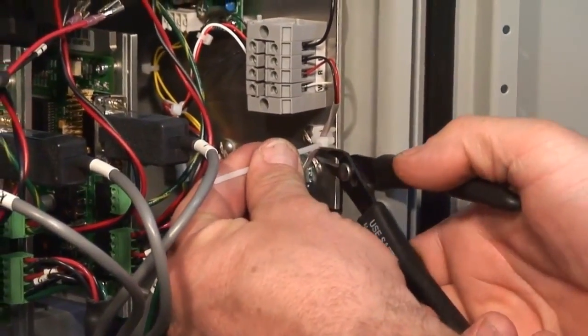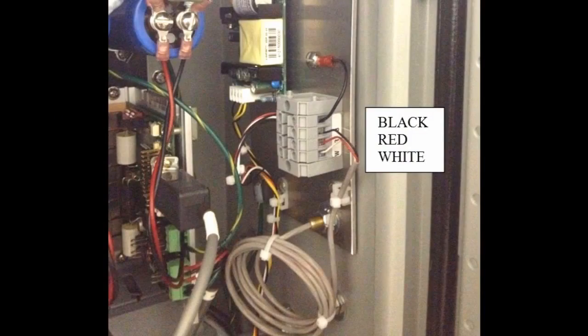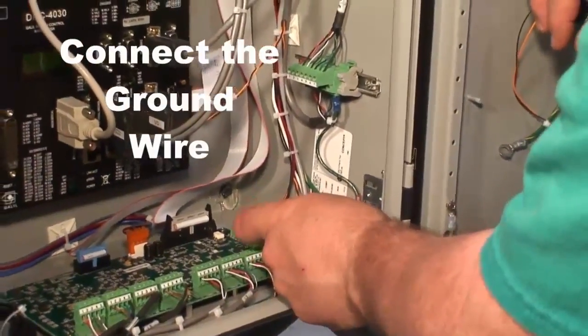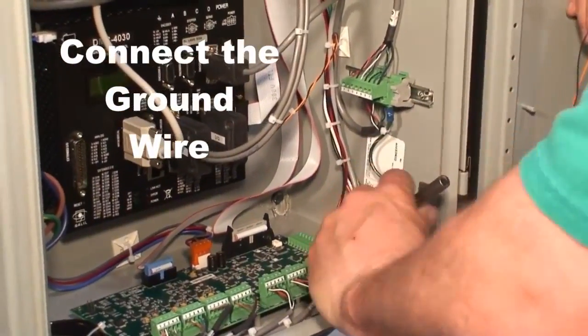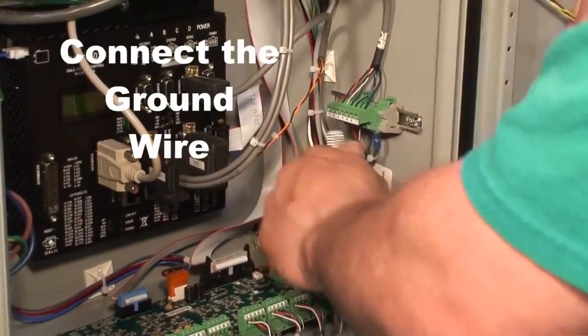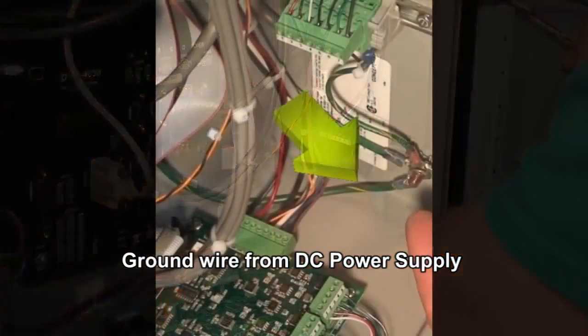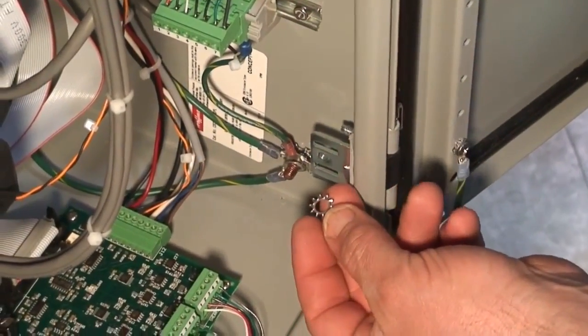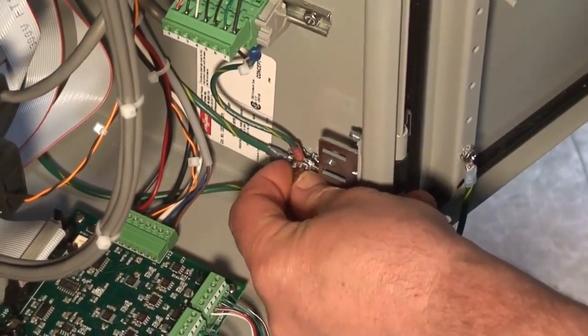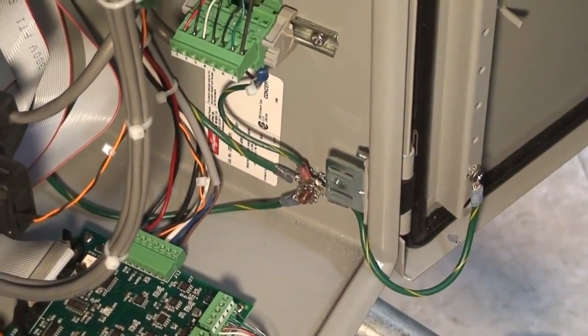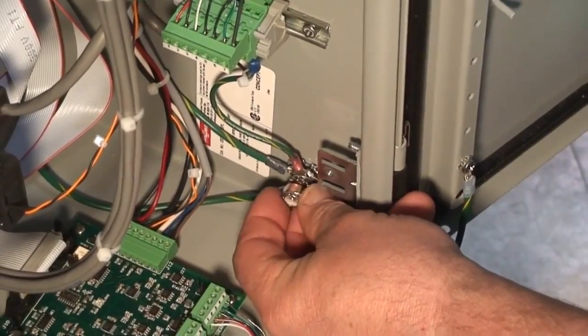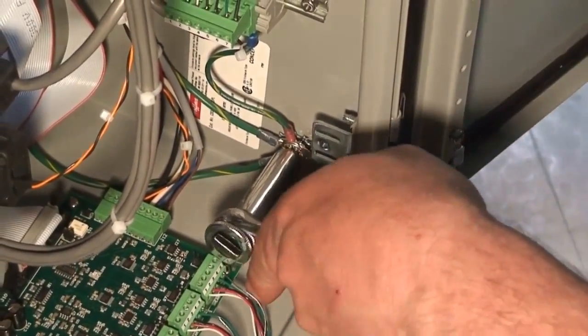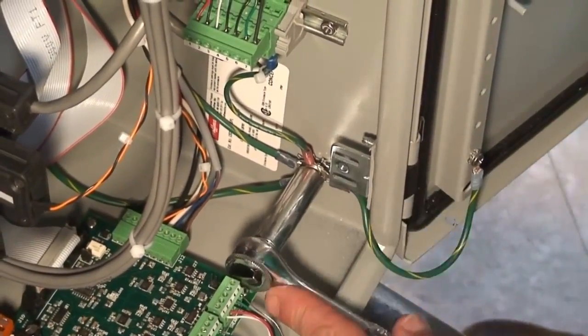Black, red, white. This is what the installed cable should look like. Now remove the nut from the ground stud in the bottom right of the box. There's a nut and star washer on here. Save those. This is the ground wire from the power supply. Put it on the ground stud. Put the star washer back on, put the nut back on, and tighten the nut. Be careful not to over tighten it. You can easily twist the stud off the box.